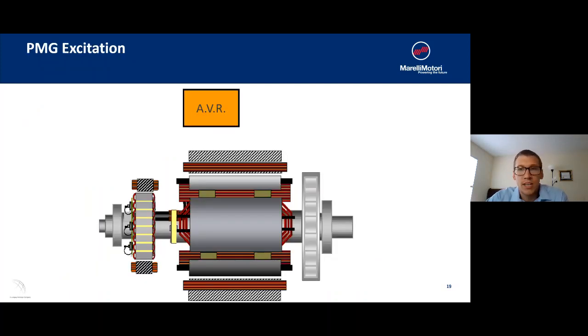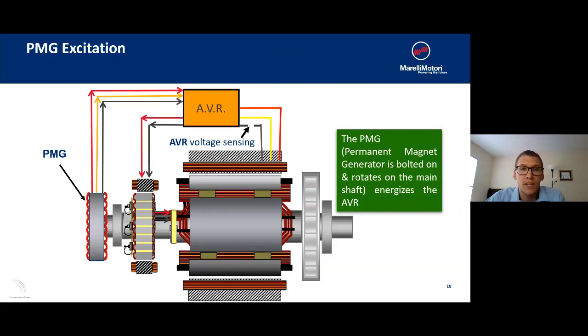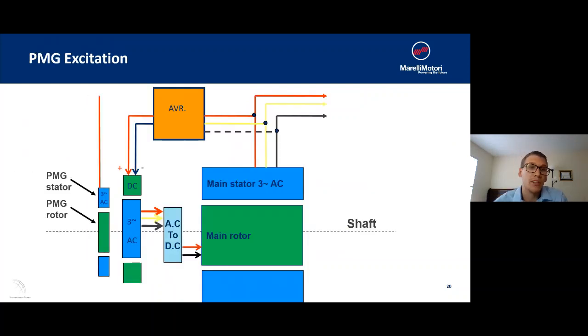For PMG excitation, it's very similar to the auxiliary wound, where you have the AVR feeding the exciter stator and sensing the voltage that's coming out of the main stator. But the only difference is that PMG is what's going to be feeding the AVR. So any dips you see from the current is not going to affect the feeding of the AVR. So it's a much cleaner signal, much cleaner voltage. And here's another example of where we're going to see the three-phase and the single-phase AC and DC currents, where you're having the AVR feed the DC current into the exciter stator, inducing it into the main rotor.